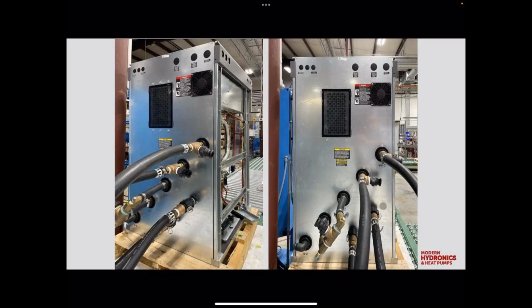People that are familiar with our original variable speed water to water will notice that there are 2 more ports right down here. Those ports, if ordered in the dual fuel configuration, will have plugs in them. But this is where you hook supply and return from the boiler. So we're actually piping the boiler directly to the back of the heat pump, and then the boiler can back up space heating as well as domestic hot water.